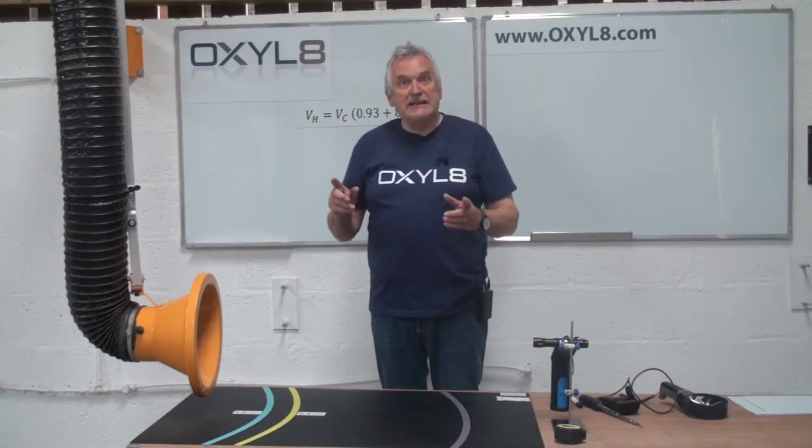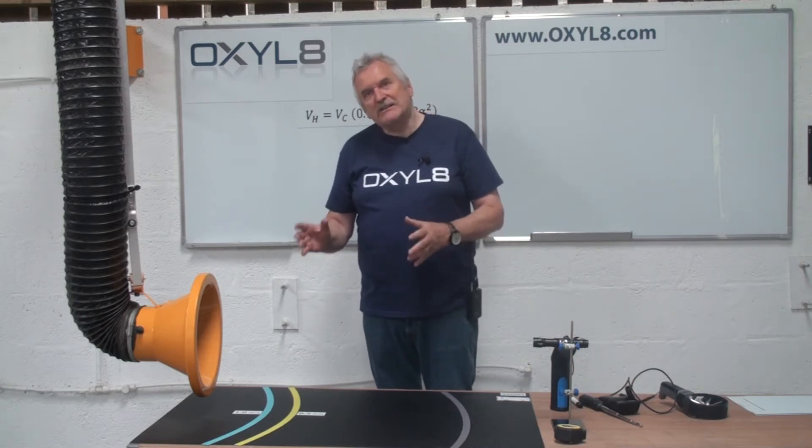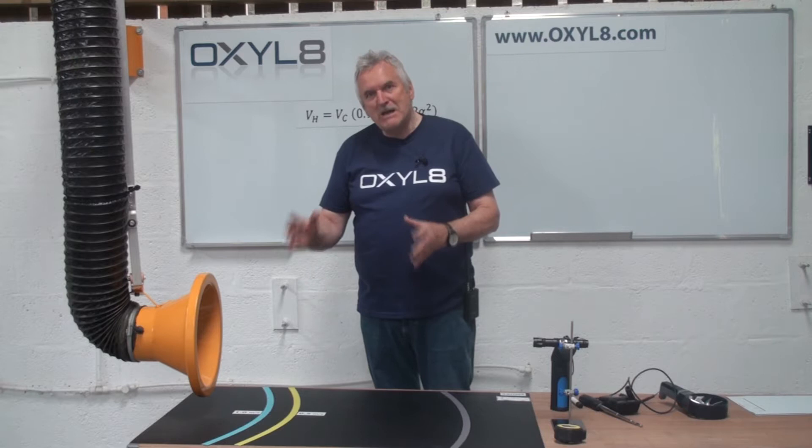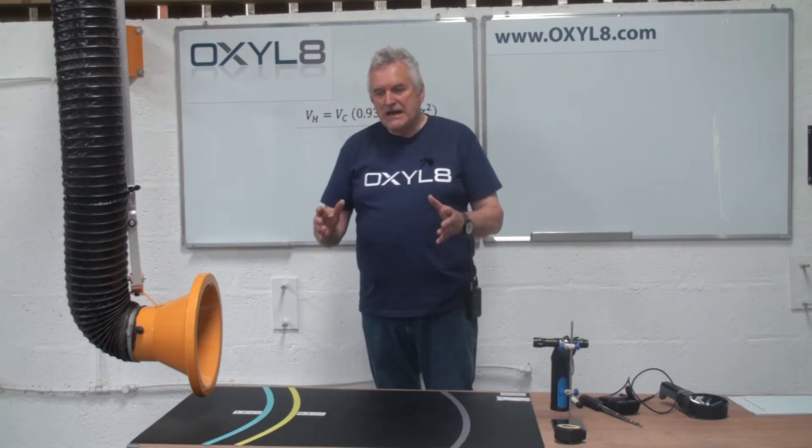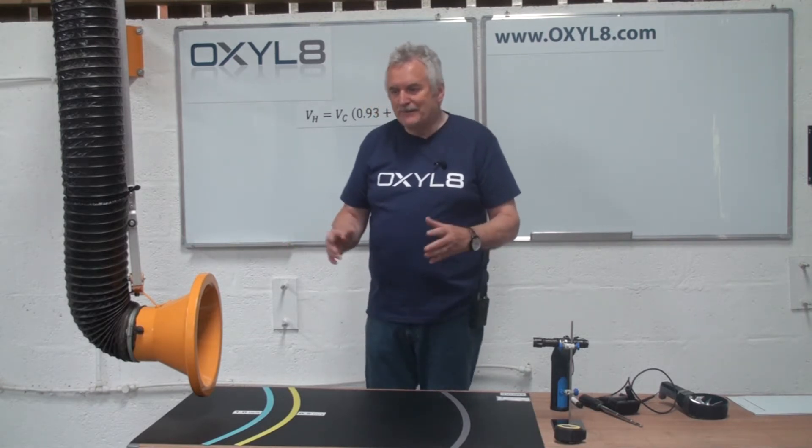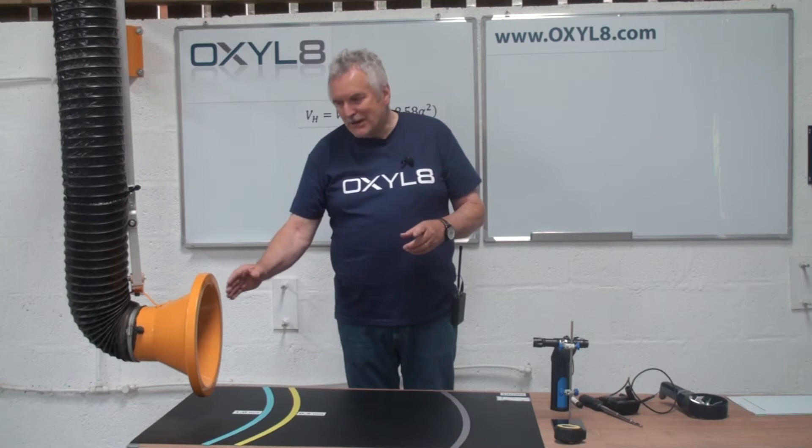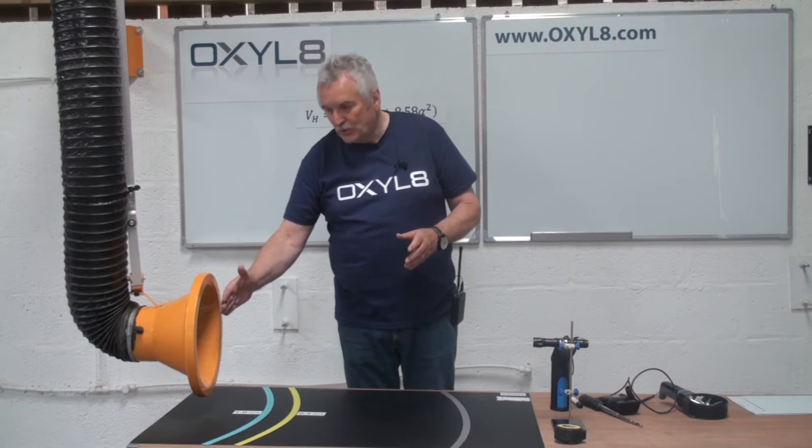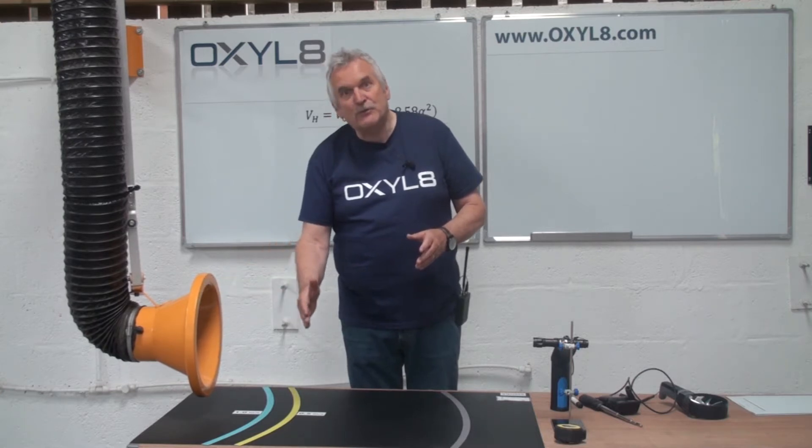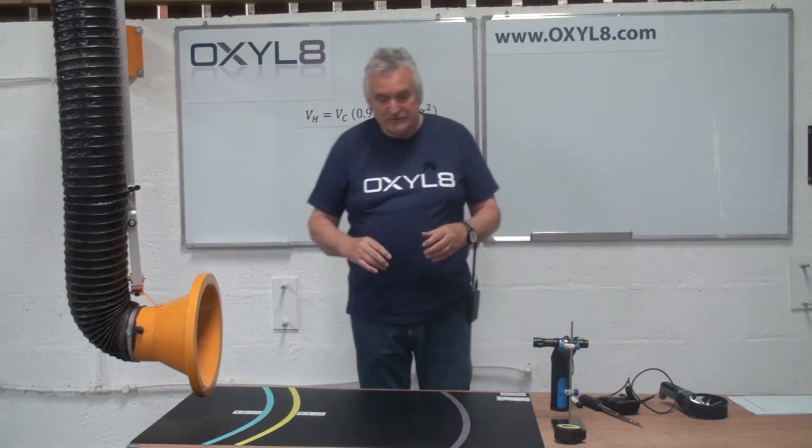Welcome to the second in the captor hood series, we're calling it Captor 102, where we're going to consider how we would physically measure the performance of a hood, captor hood, the captor distance, and therefore the control area. What we talked about in the previous video was that there are ways of calculating how quickly the velocity at the face will reduce as it comes away from the hood entrance. Fletcher's nomogram gives us this equation.